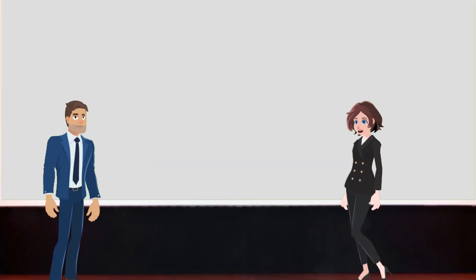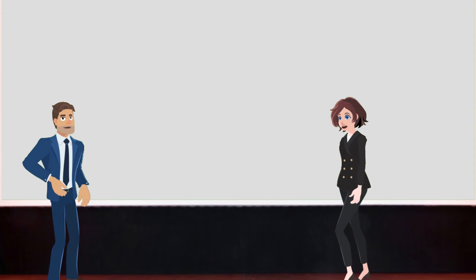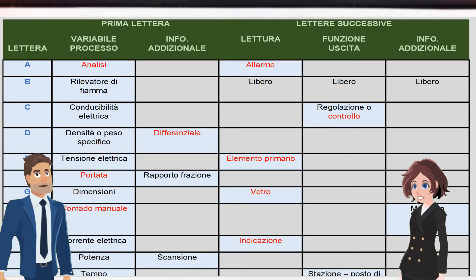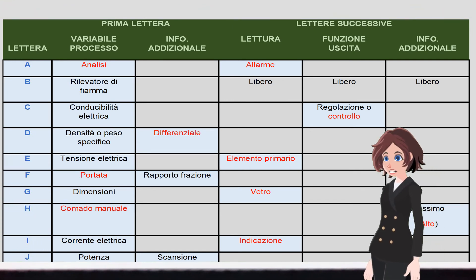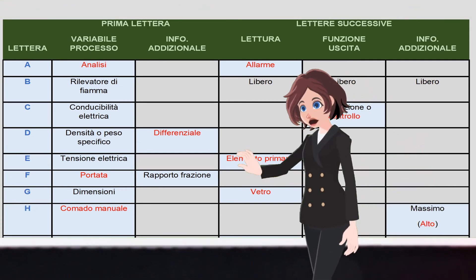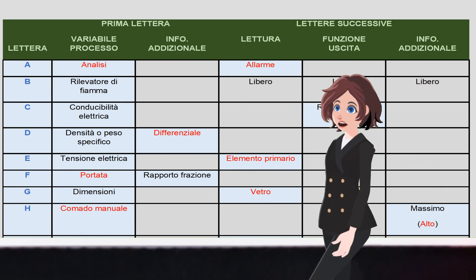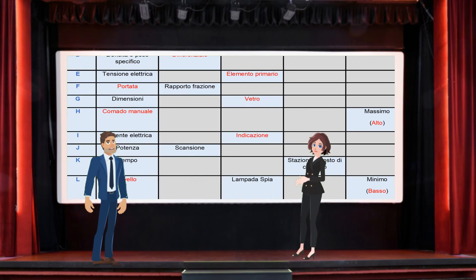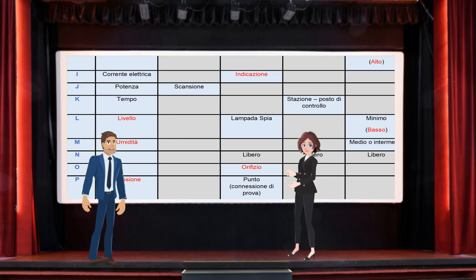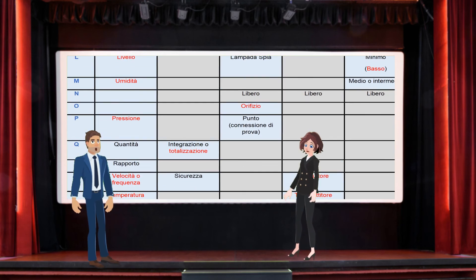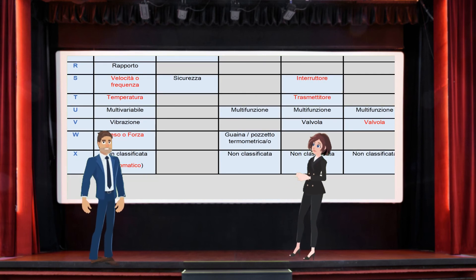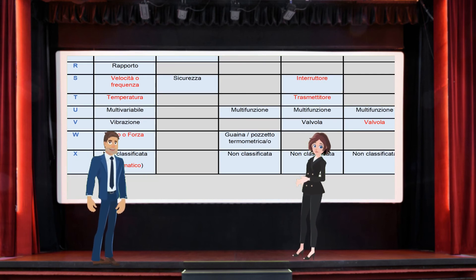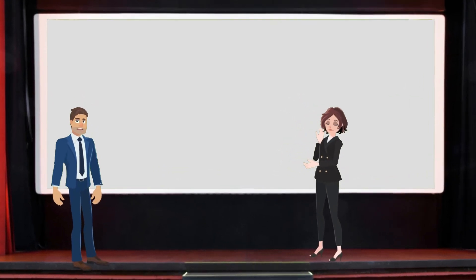Each instrument is identified through a combination of letters where the first letter represents a process variable. Some examples are: P for pressure, T for temperature, Z for position, A for analysis, F for flow rate, L for level, and so on. The second letter defines what the instrument does and what it is — for example, I for indication, C for control, T for transmitter, A for alarm, S for switch. From the third letter onward, additional information is indicated, for example L for low, H for high, V for valve.